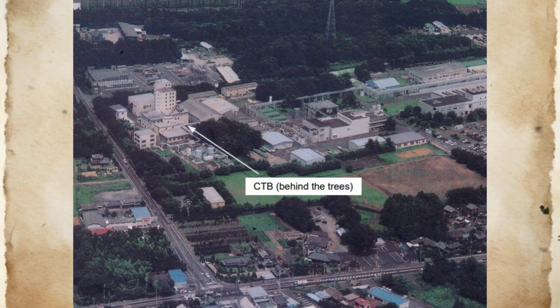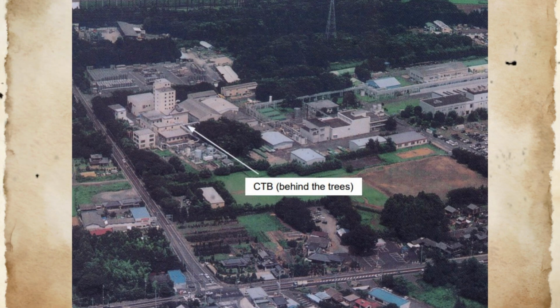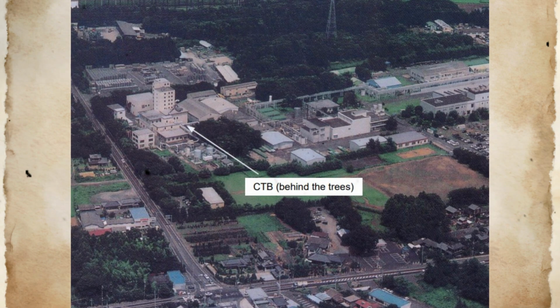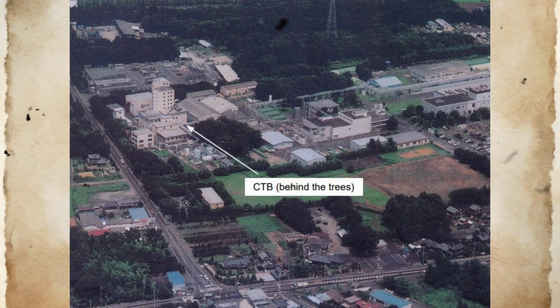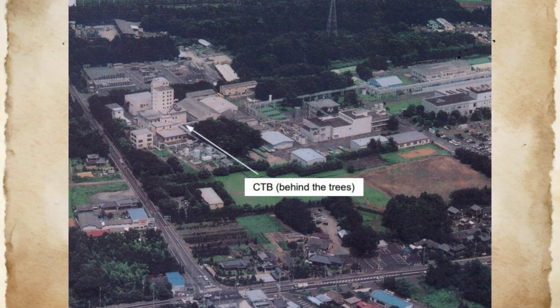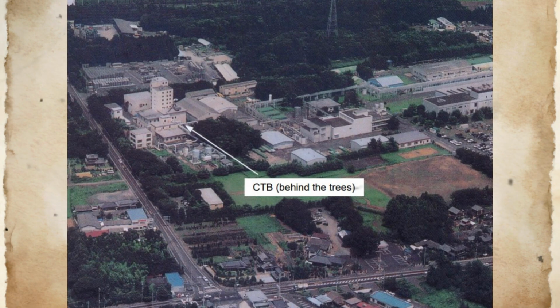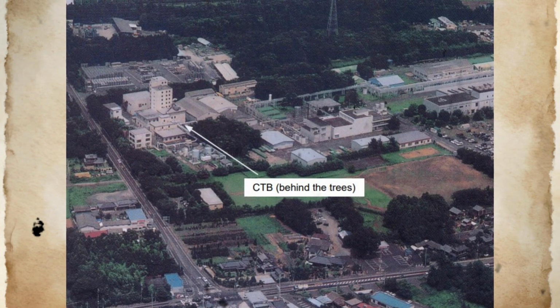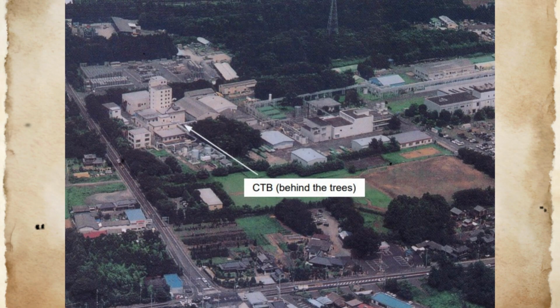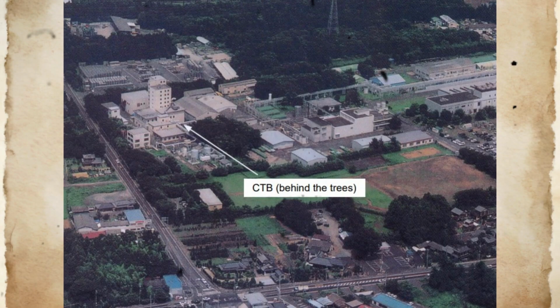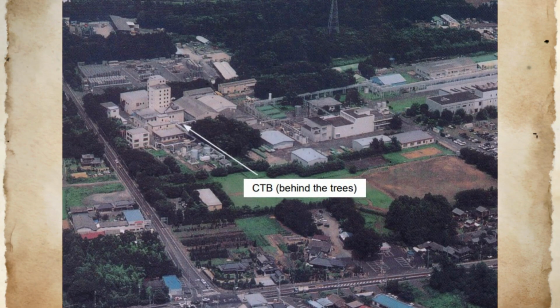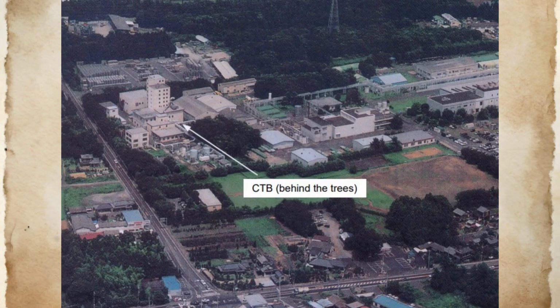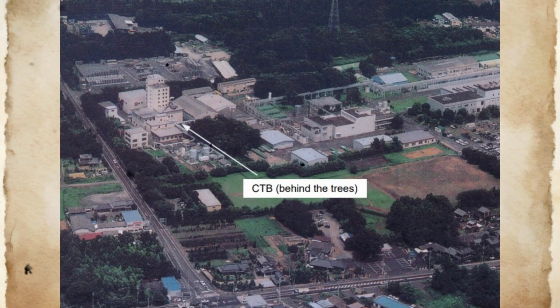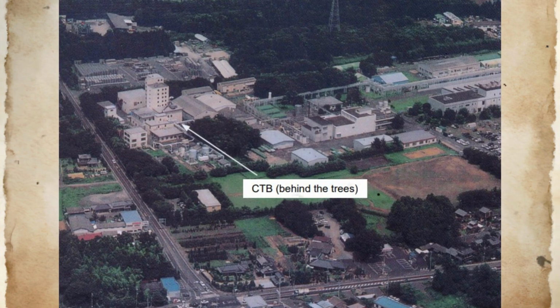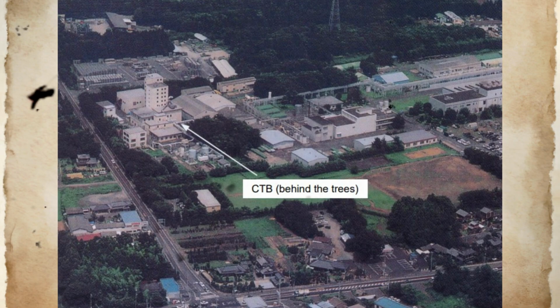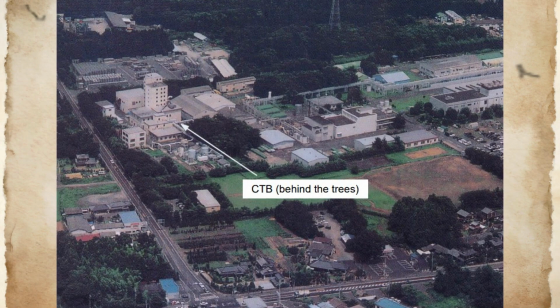Approximately 19 minutes after the earthquake, operators manually closed the isolation condenser outlet valve to reduce the cooling rate in compliance with technical specifications that limited reactor temperature decrease to 55 degrees Celsius per hour. This action reflected appropriate adherence to established procedures and demonstrated that operators retained control over plant systems during the early phase of the emergency. The manual operation was based on the reasonable expectation that other cooling systems would be available to resume heat removal at acceptable rates.